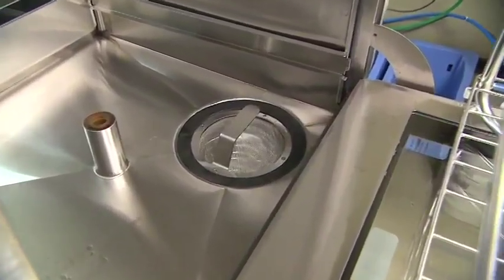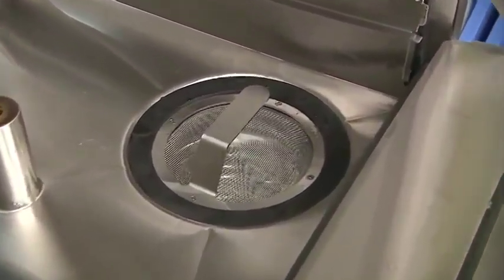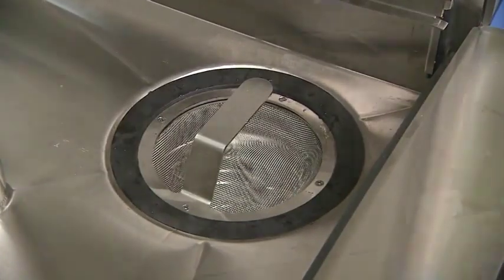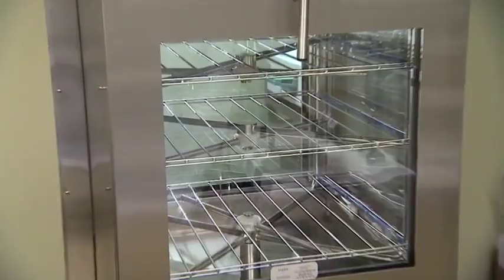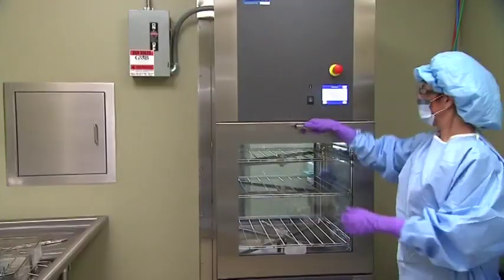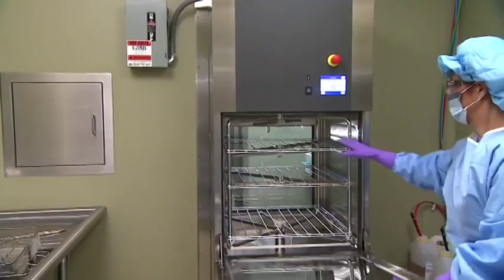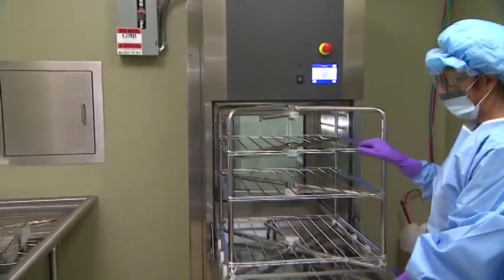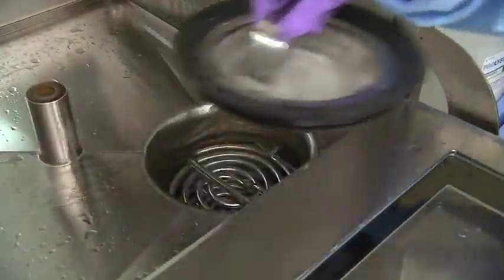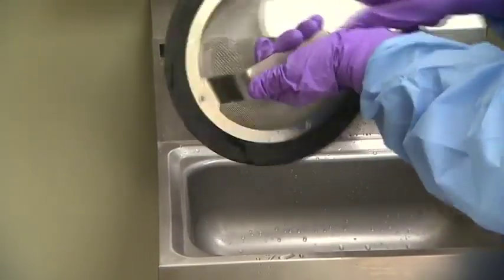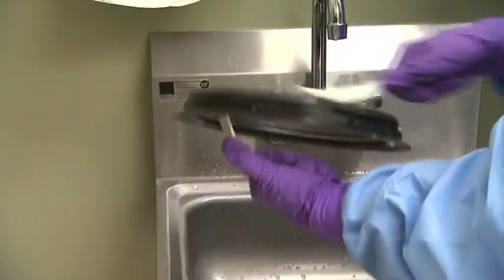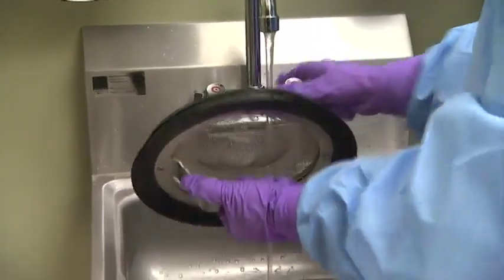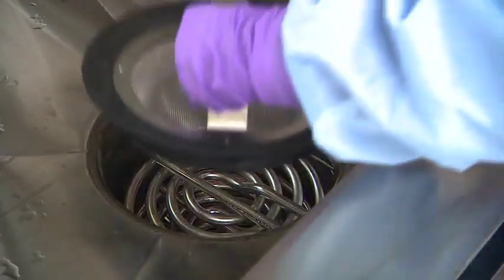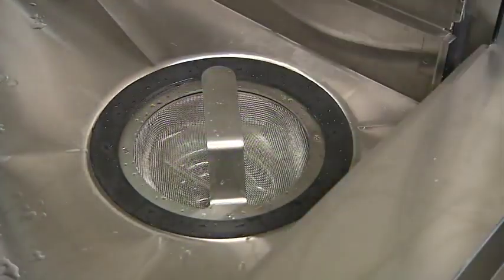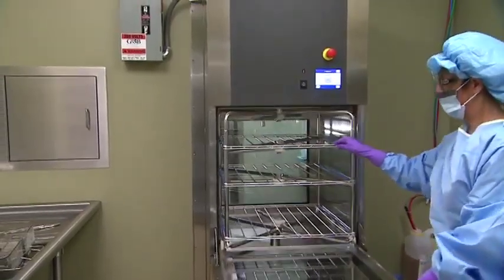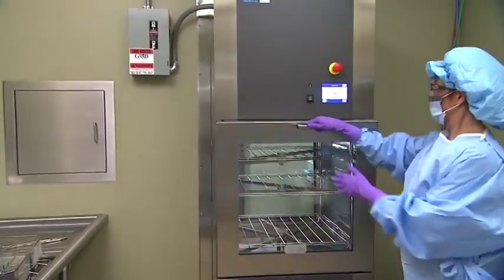After the last cycle of each day, clean the debris screen located in the bottom of the sump. Here's how. Allow the washer disinfector to cool down before reaching into the chamber. Carefully open the chamber load door. Pull the manifold rack out of the chamber and onto the chamber door. Remove the debris screen and always clean it while it is still wet, before the debris dries. Brush the screen to detach the dirt. Then rinse it under running water and reinstall it in the sump. Press firmly into place and, when finished, roll the rack back inside the chamber and close the chamber load door.